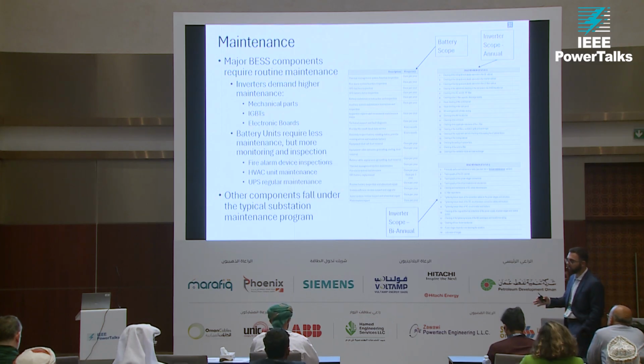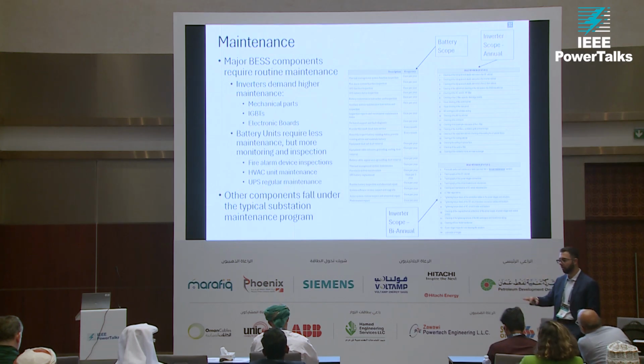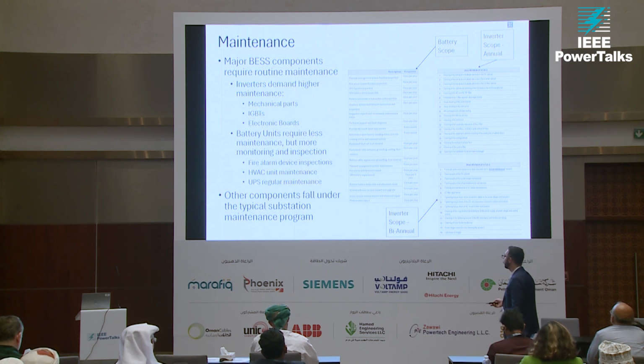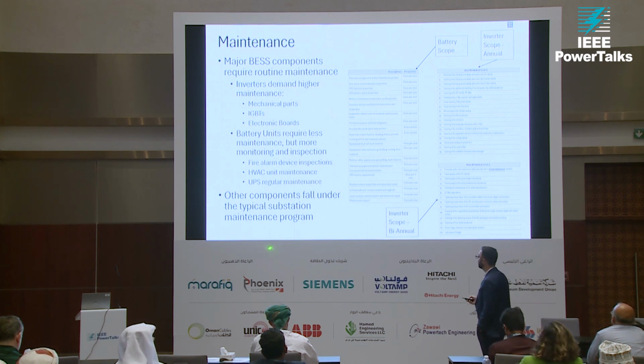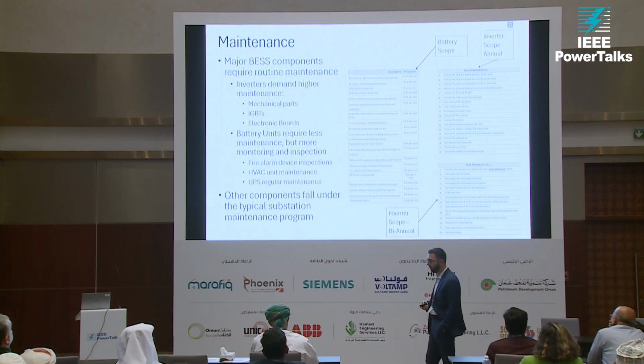And when I say go there, you don't really physically need to go there. Those are reported remotely. You can do analysis from your office and make sure that the trend is not getting worse over time. With the battery systems, it's very similar. It's really inspection based.